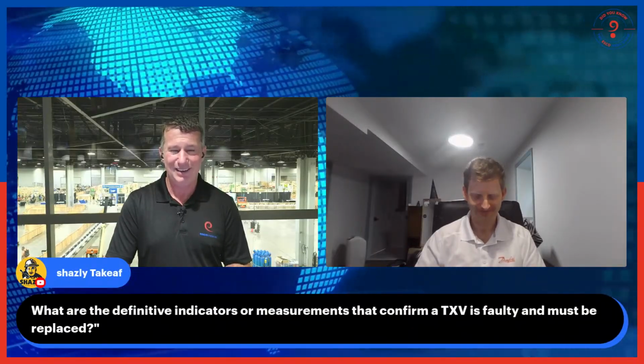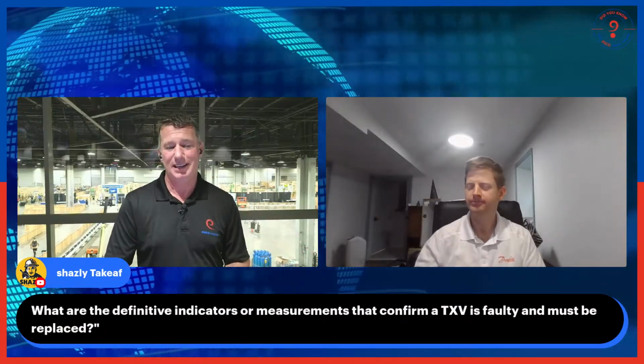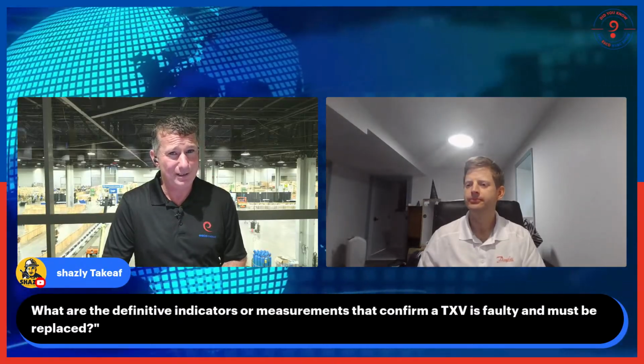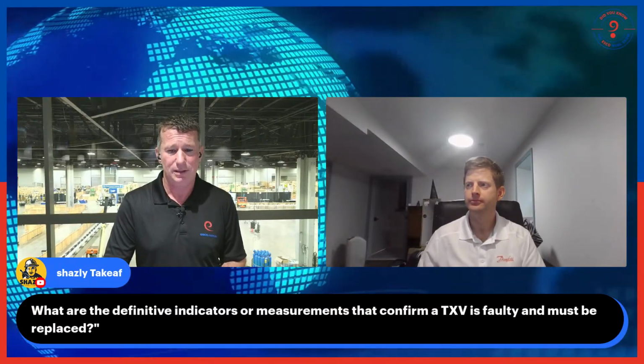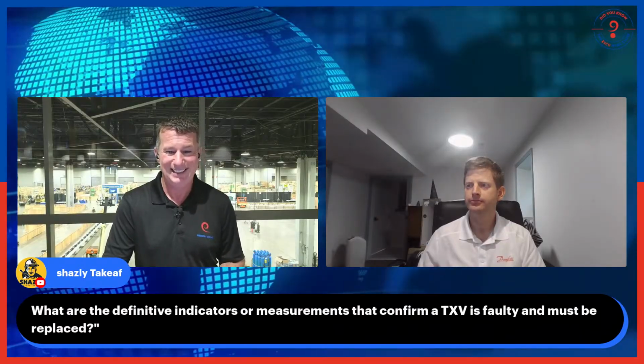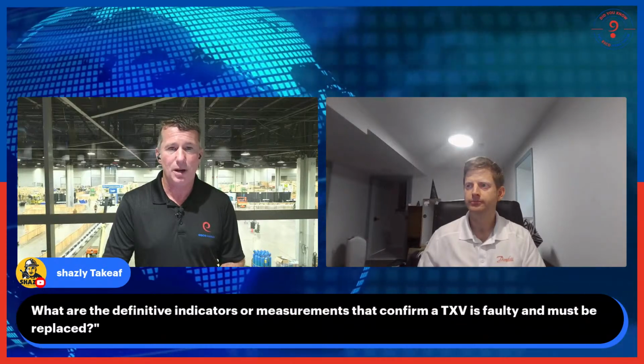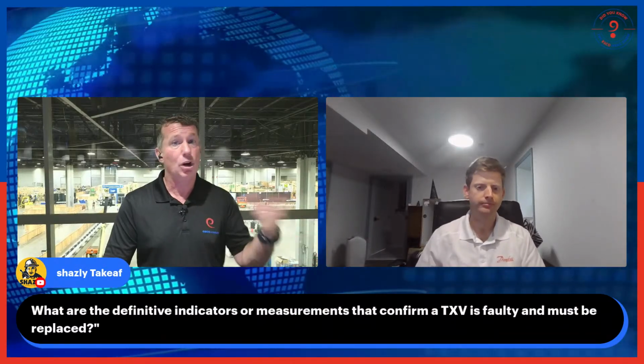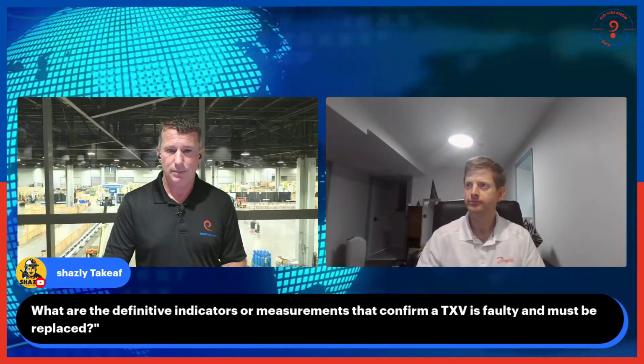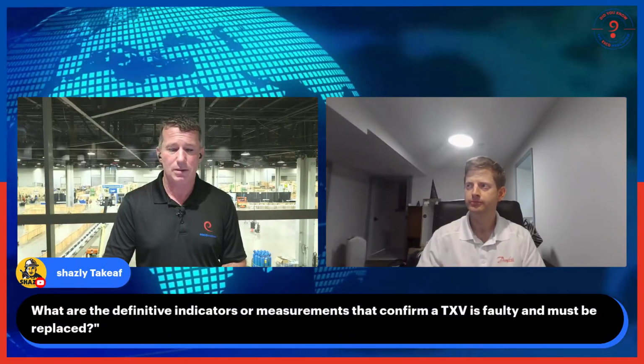Oh, yeah, that is a great one. And that is actually probably a whole conversation that we can have. It goes back to the same conversation of operation. I have only found very few, probably less than a handful, of thermostatic expansion valves truly bad in the industry. They could have been damaged from improper installation, but typically they're a very reliable operating instrument. Now, the variables that can cause it to adjust, on the other hand, could be the things affecting it. So we always start with standard practices. Is airflow correct? Then we can move on to, is refrigerant charge correct, and how are our superheat and subcooling working? But the airflow across those coils is always the most important thing to check on any thermostatic expansion valve.